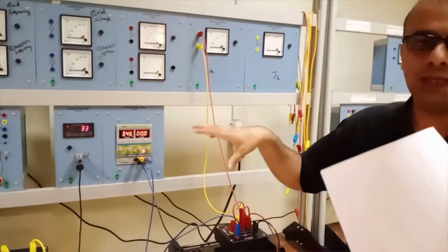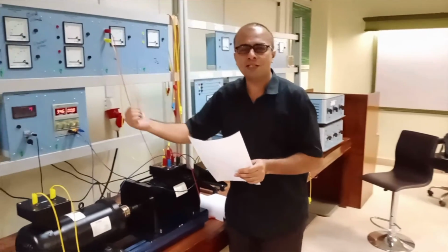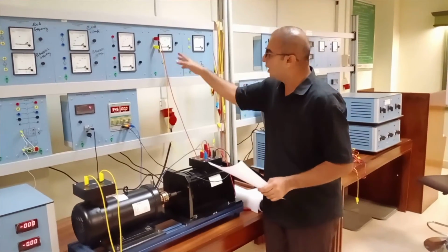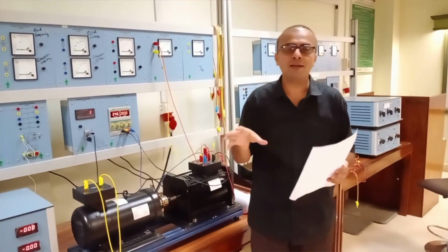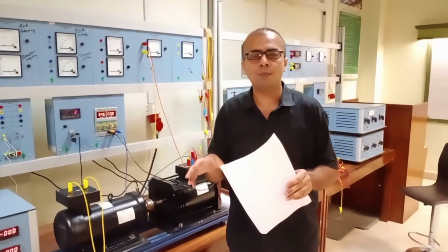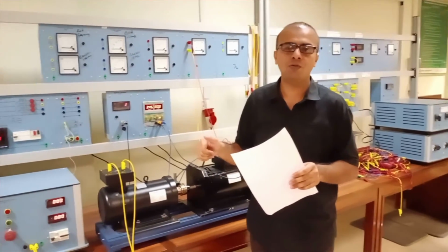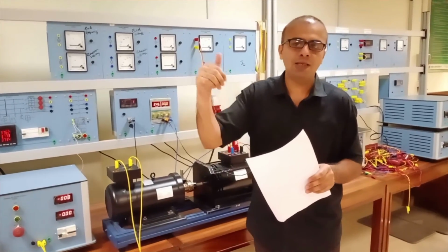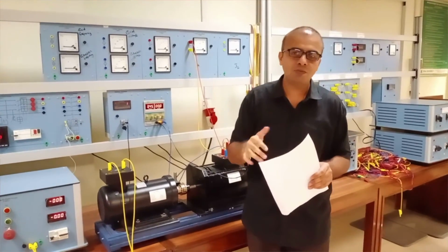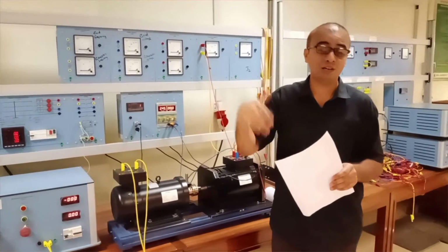Now we have concluded from this open circuit test of the alternator that if we increase the excitation, the lines of cut of the magnetic field will be maximum in the rotor winding, and the stator voltage is increased. Already you know that the terminal voltage of the alternator can be easily maintained by the field excitation given to the DC field winding of the alternator. So increasing the excitation increases the stator terminal voltage, and decreasing the excitation decreases the stator terminal voltage, by which we can easily maintain our terminal voltage for the parallel operation of alternators in our power plants.